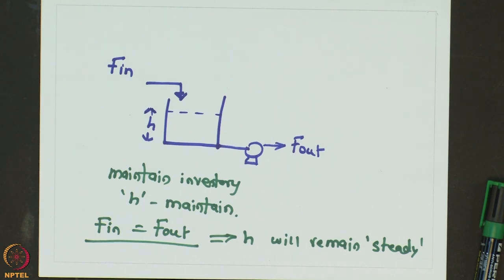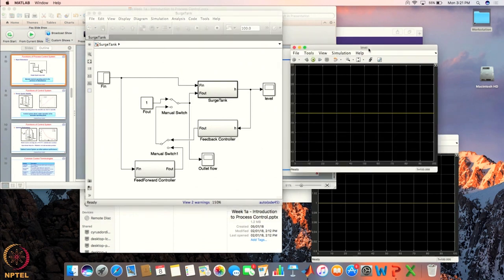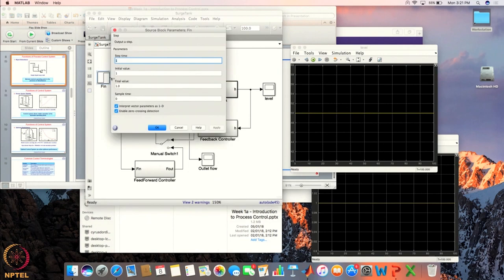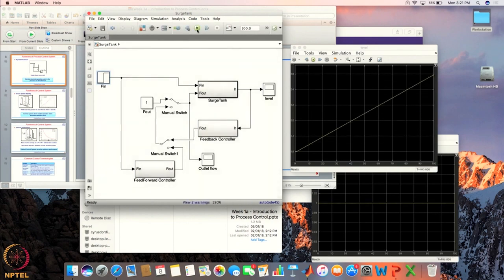Let me explain that using a small simulation. Here is the model for this particular storage tank. If F_in, the inlet flow rate, remains constant and we run it for a long time, you can see that the height inside the tank also remains constant at the desired value of 50. But since there is no control over F_in, the inlet flow rate may increase or decrease. If the inlet flow rate increases by 5 percent and we do not take any control action, the level inside the tank will keep increasing linearly, and after it reaches 100 percent the tank will overflow.